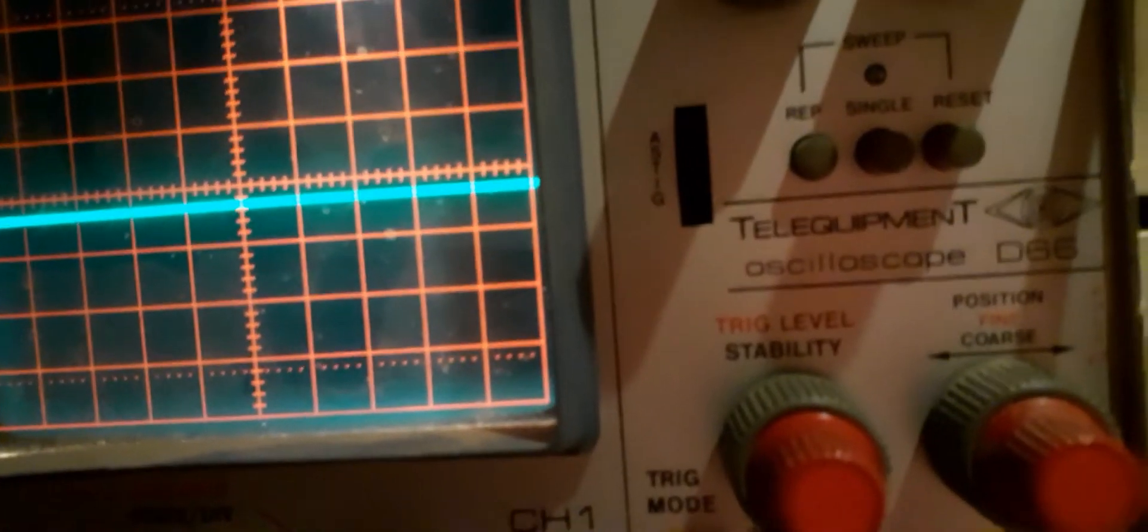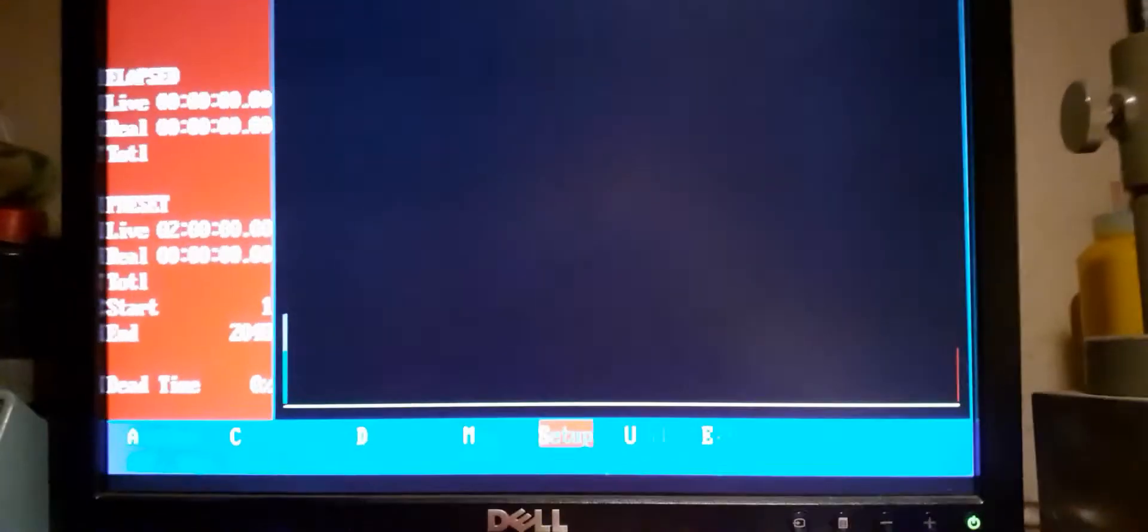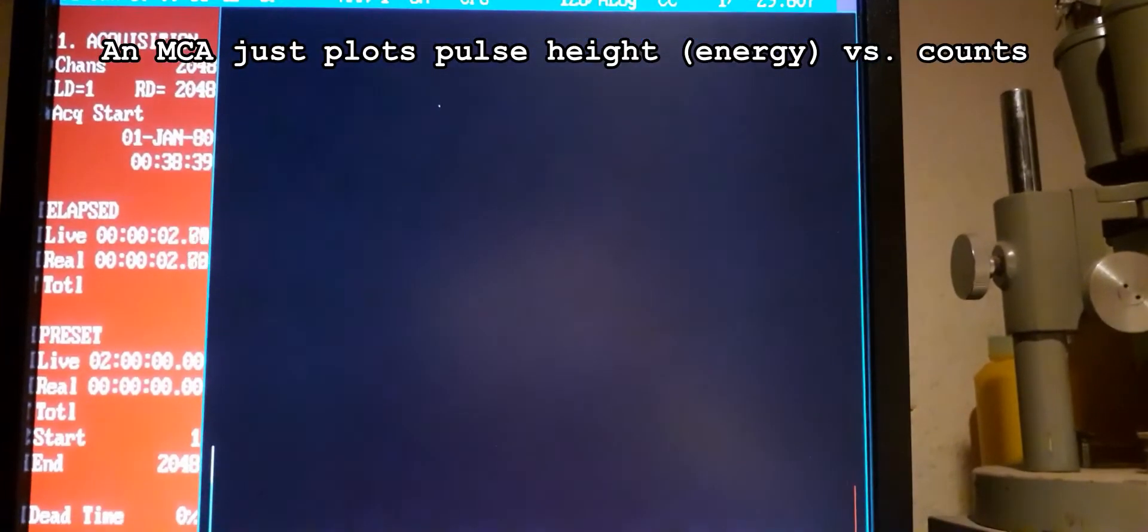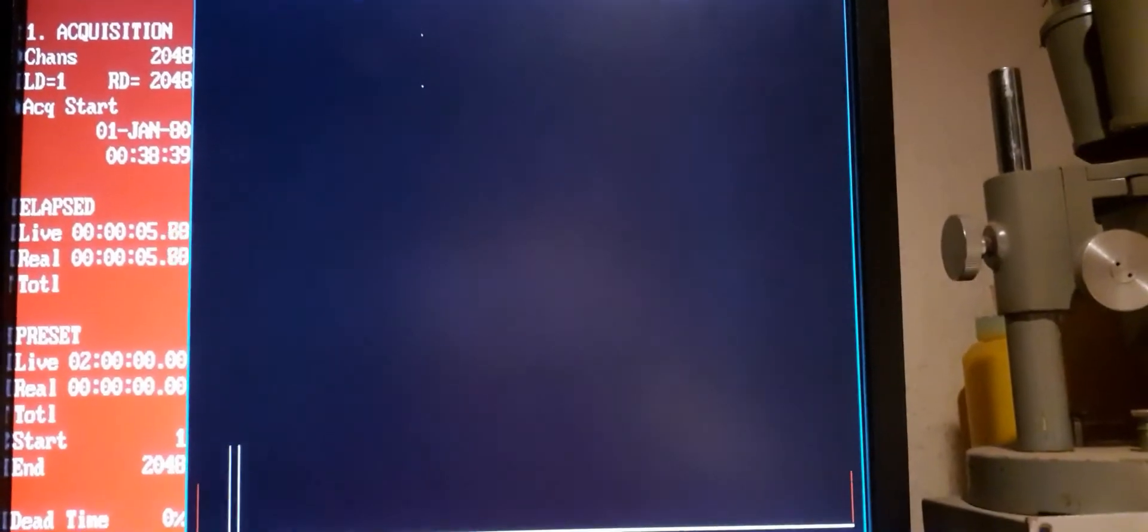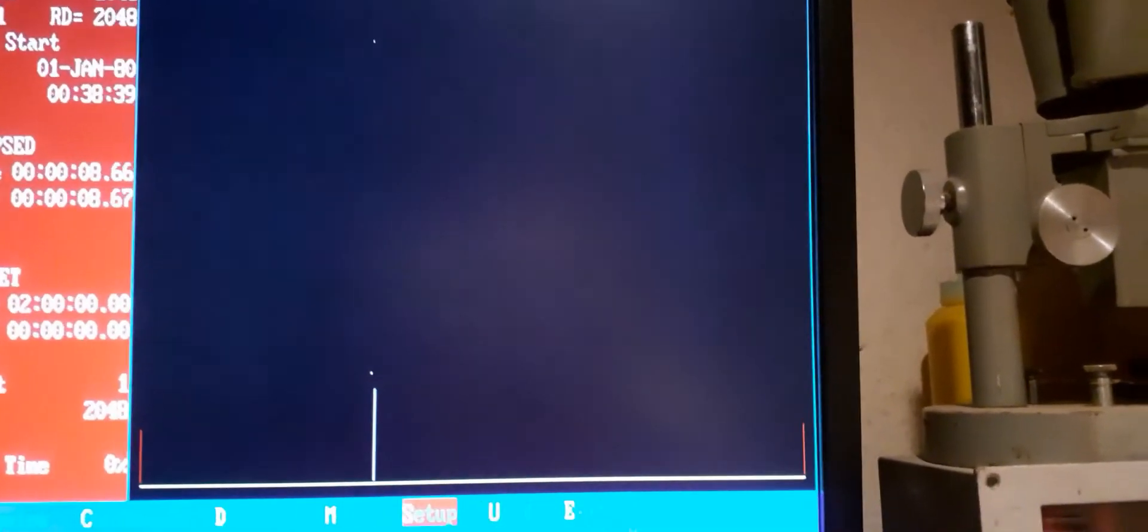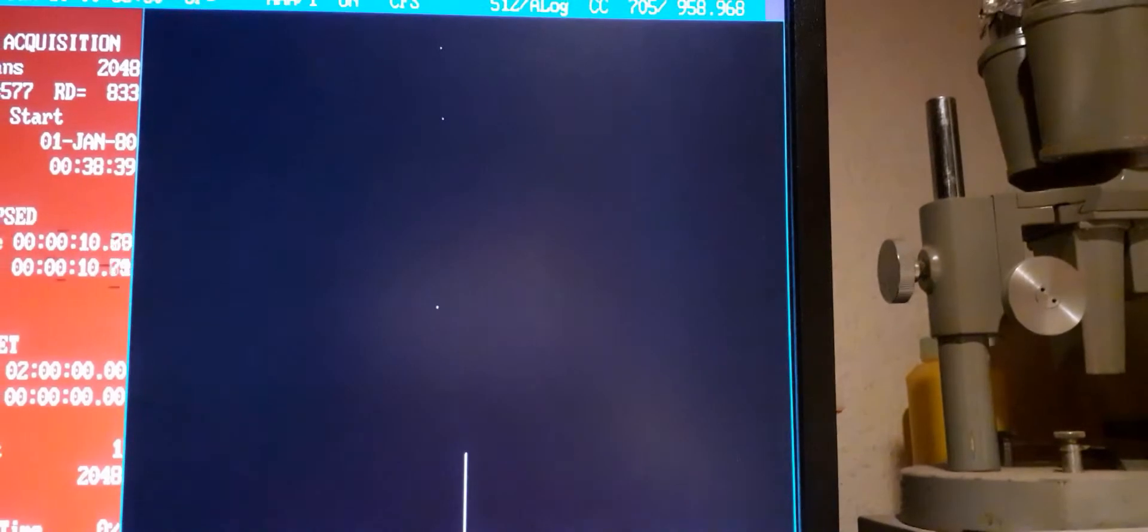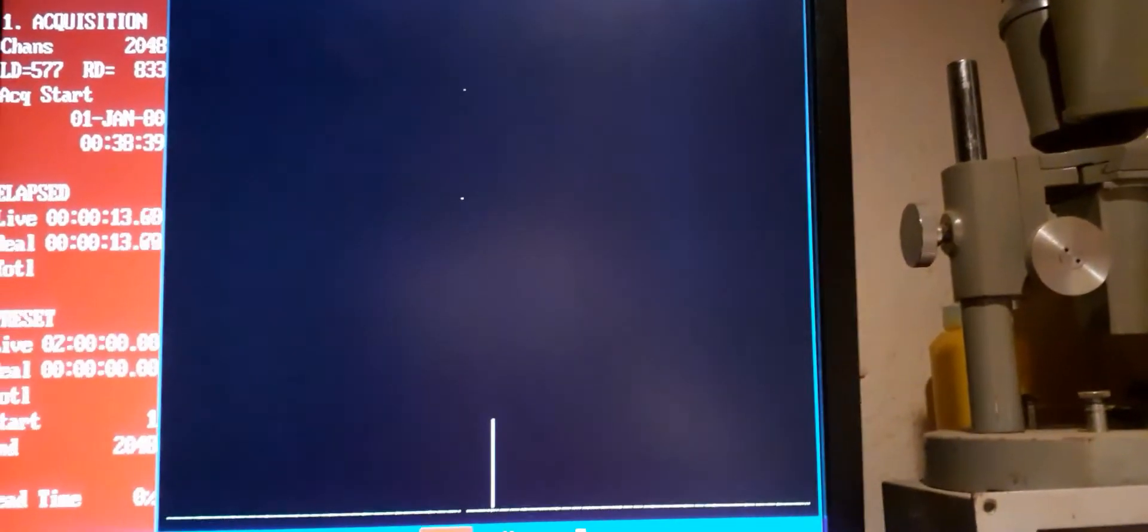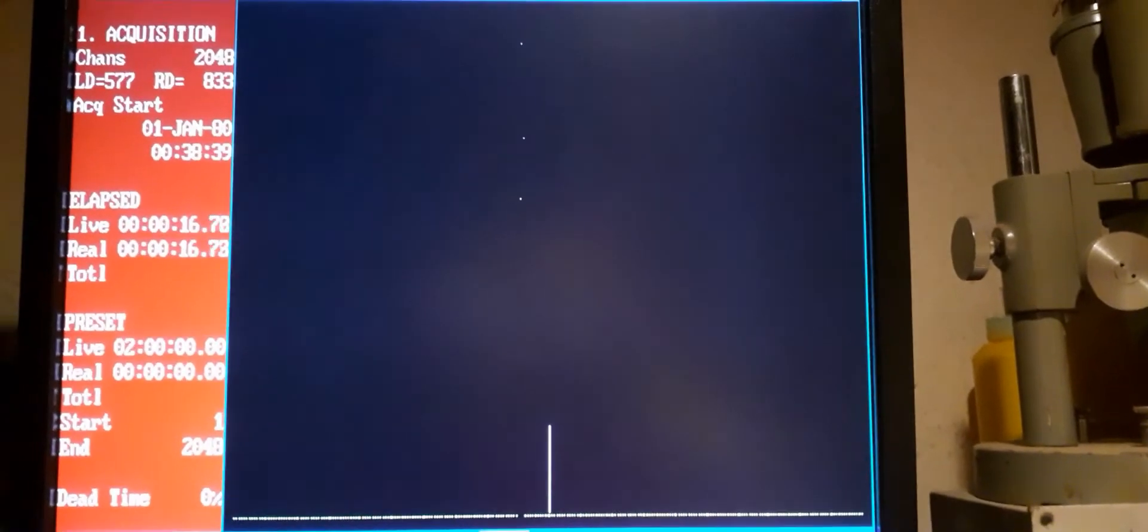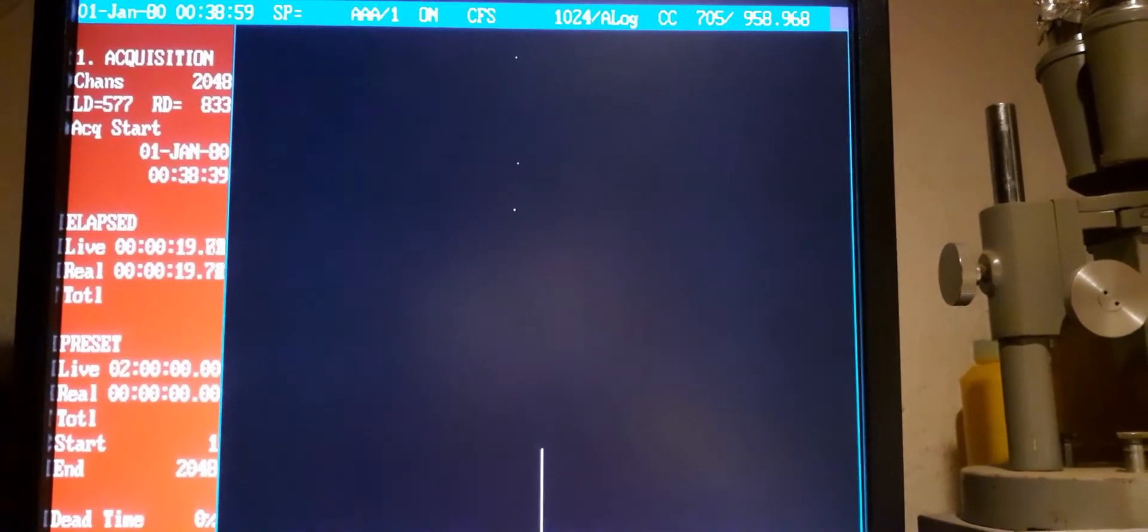Now let's try to add in the multi-channel analyzer and actually see if this analyzer isn't drifting—it should just give a single peak. This is the cable to the multi-channel analyzer. This is a multi-channel analyzer, and we can just do an acquire. Look at that, look at that. This is exactly what you're supposed to see.